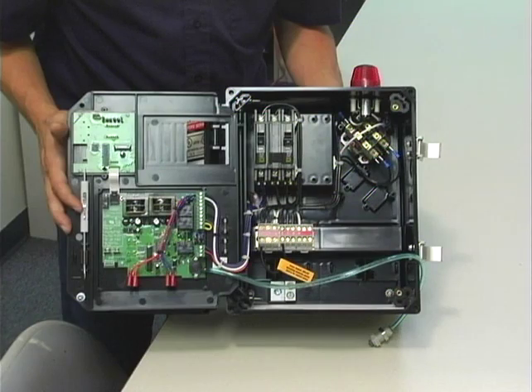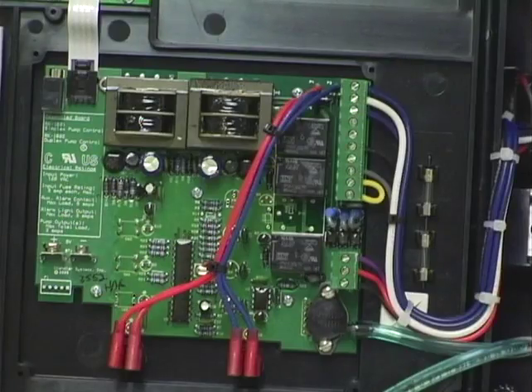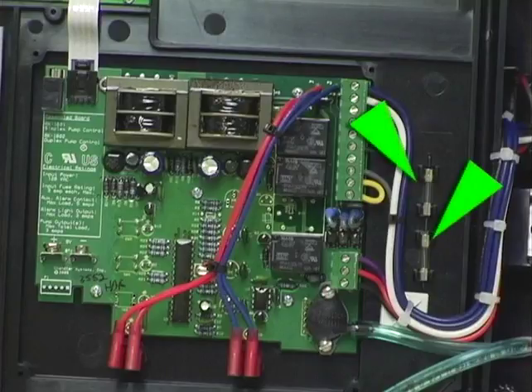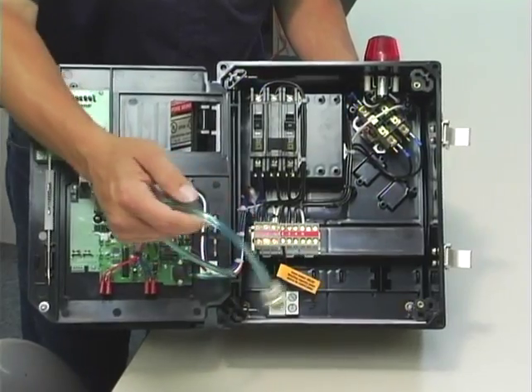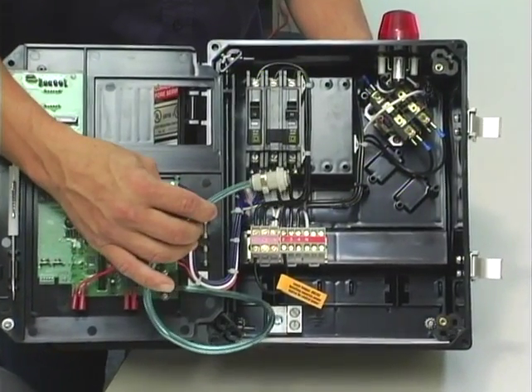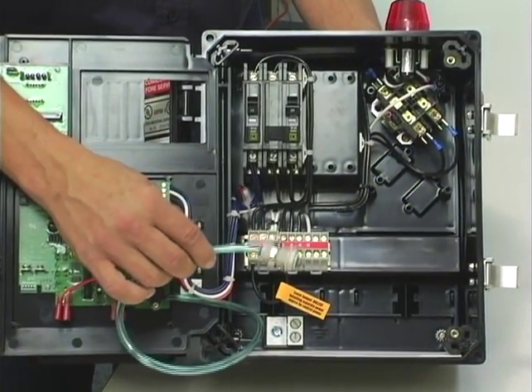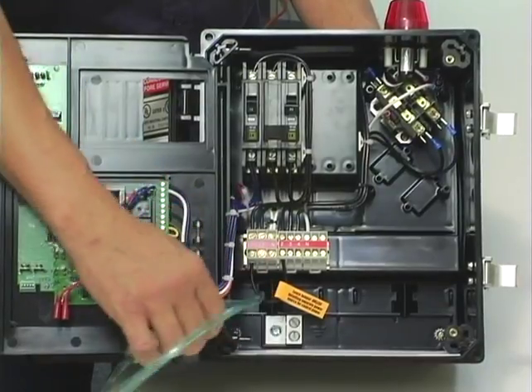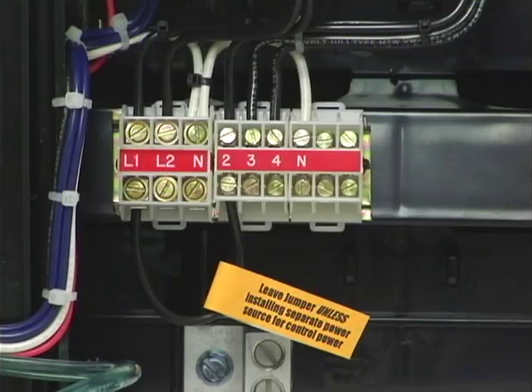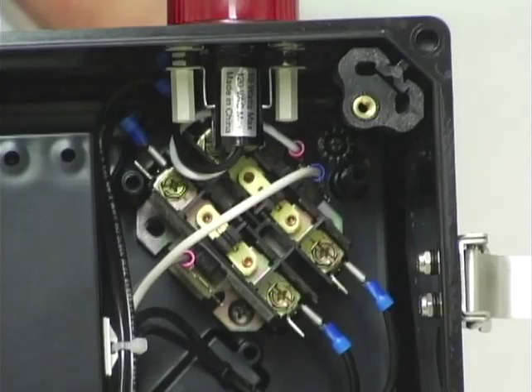If you notice, the control panel is pretty much made up of a printed circuit board on the back side of the door. You've got some spare fuses, and then you've got your airline coupling that the tubing from the pressure bell comes back. This is how the control panel tells what the depth of the water is. You've got your hookups down here for your pump and your incoming power, and your motor contactor in the corner.